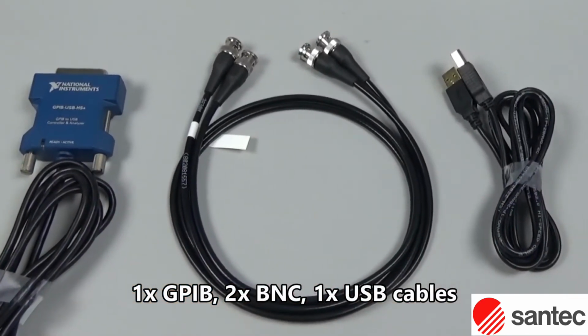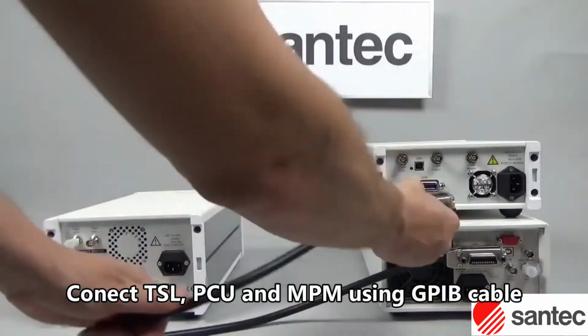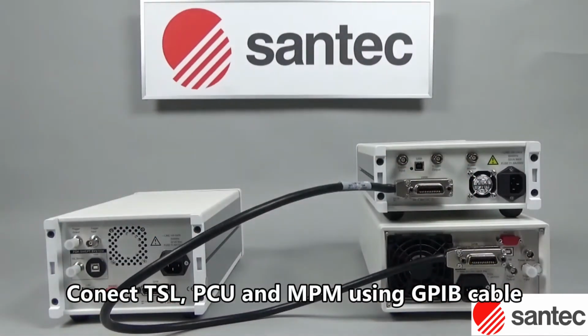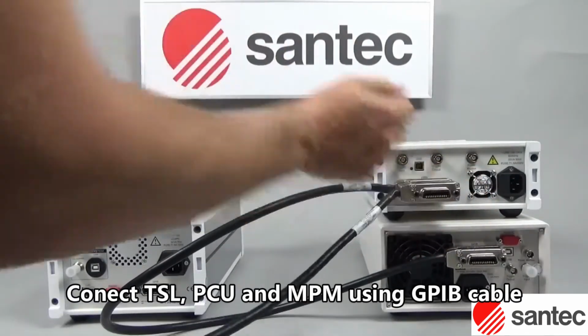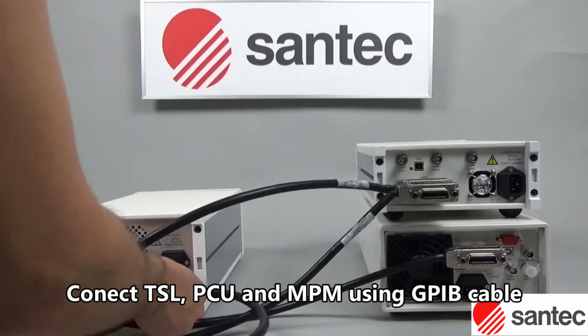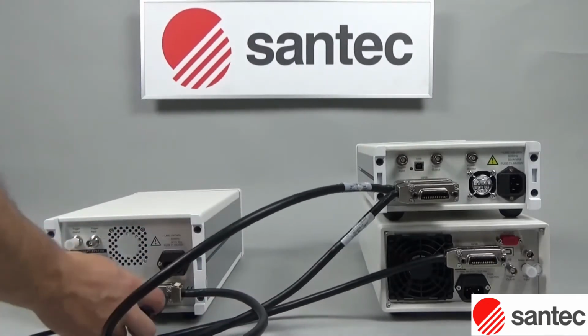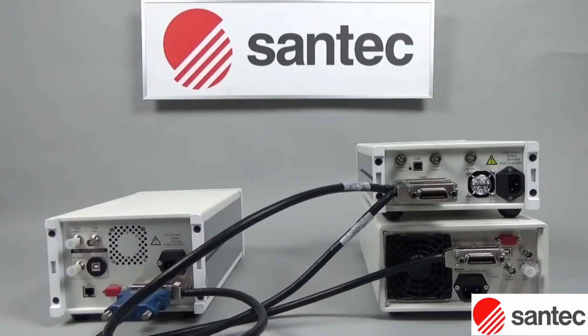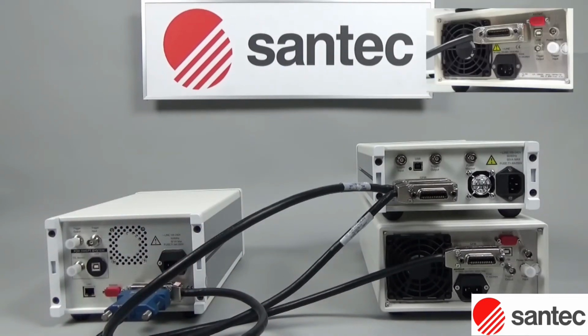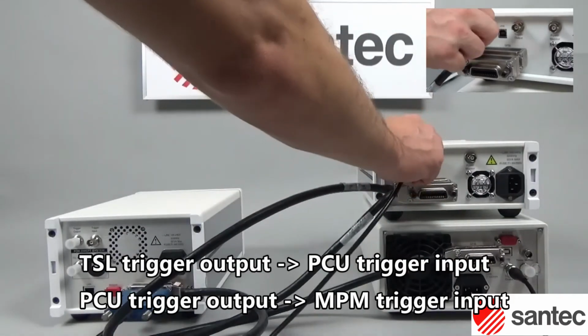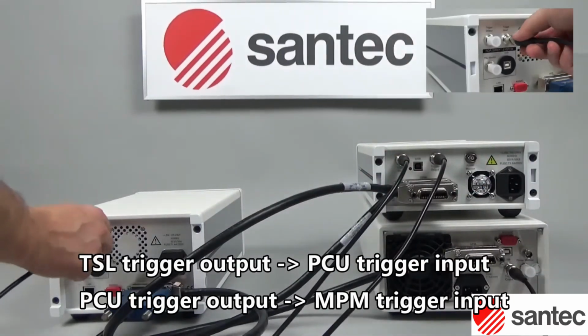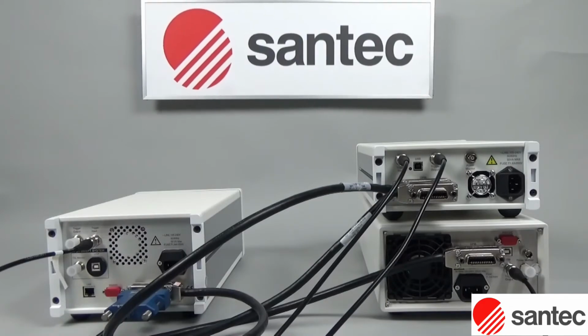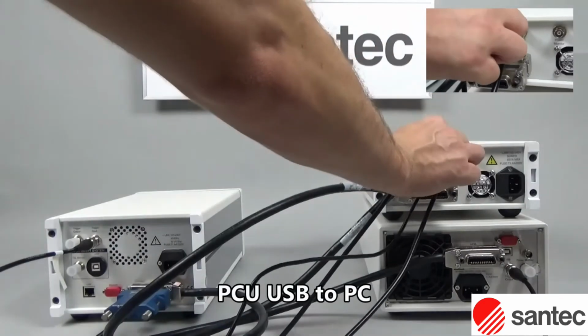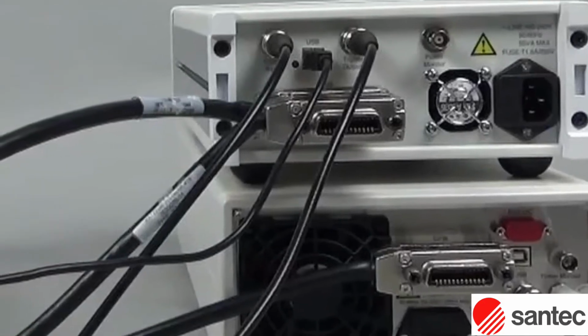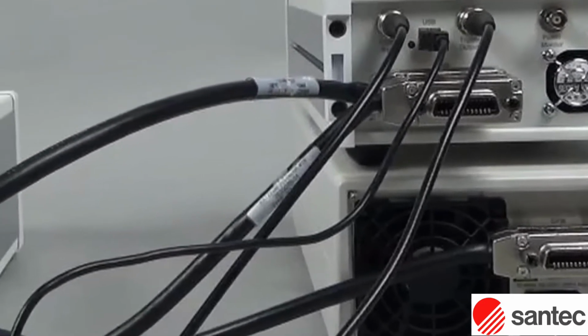Let's see the connections from the rear side. The PC will be connected to TSL, PCU, and MPM through GPIB cables. We highly recommend using National Instruments hardware. Then, from the TSL trigger output, connect a BNC cable to the PCU's trigger input. From the PCU's trigger output, connect a second BNC cable to the MPM trigger input. Finally, using a USB cable, connect the PC to the PCU's USB port. The USB cable will allow communication between the PC and the PCU's integrated data acquisition board, or DAC board.